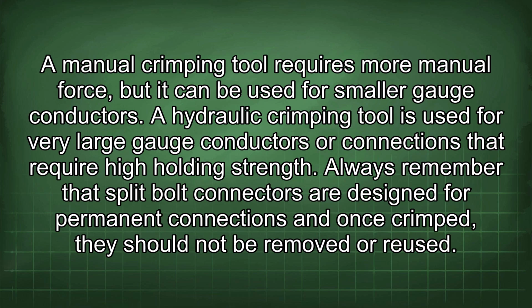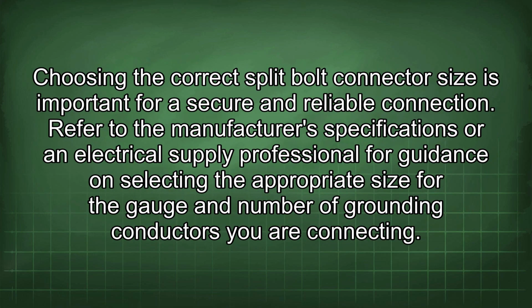Always remember that split bolt connectors are designed for permanent connections, and once crimped, they should not be removed or reused. Choosing the correct split bolt connector size is important for a secure and reliable connection. Refer to the manufacturer's specifications or an electrical supply professional for guidance on selecting the appropriate size for the gauge and number of grounding conductors you are connecting.